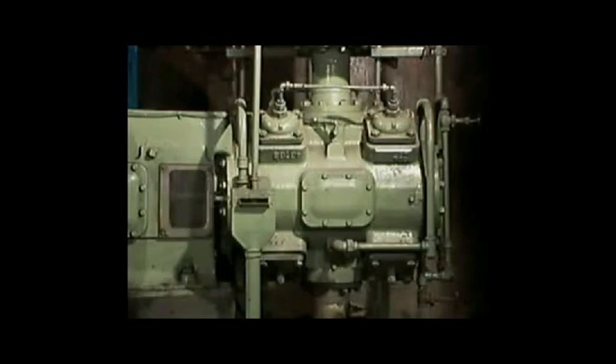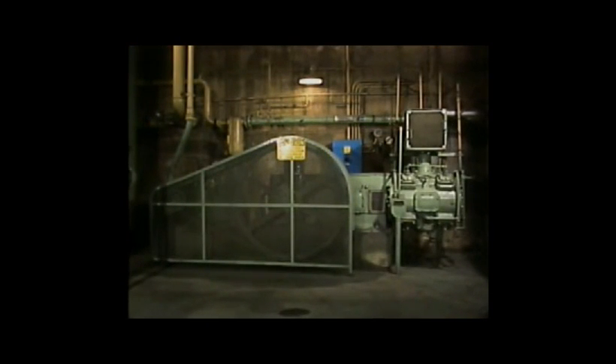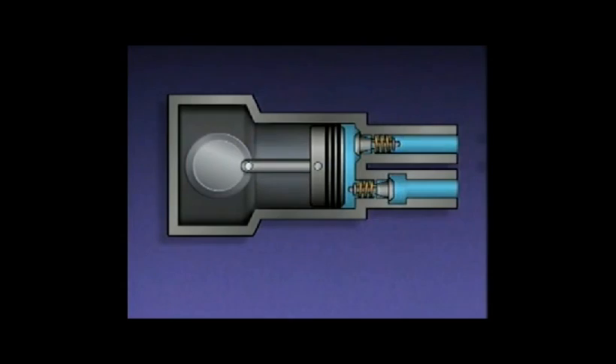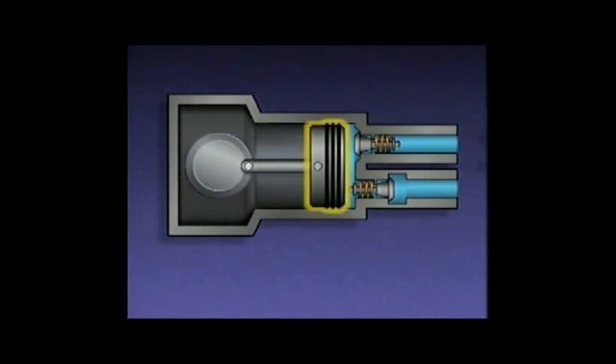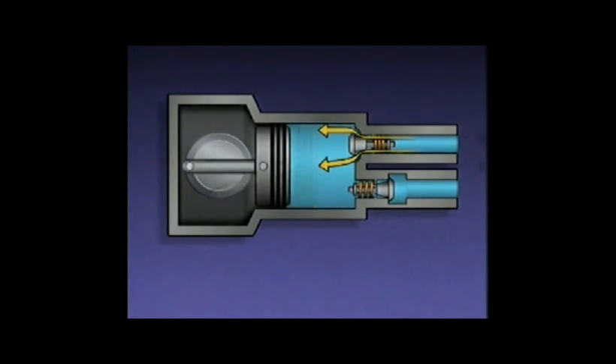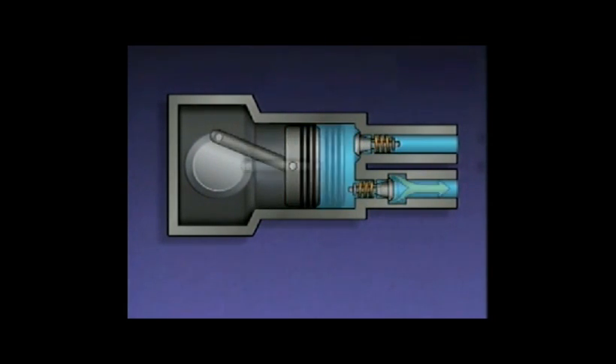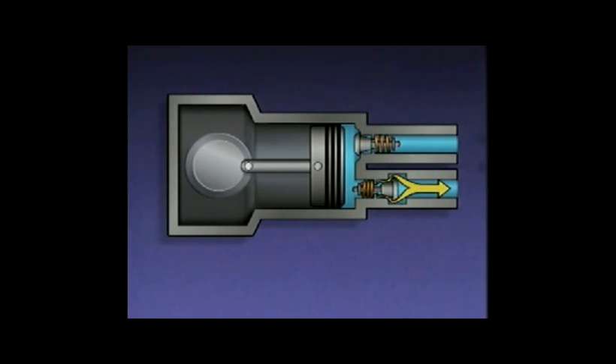Compressors can be divided into two general categories: positive displacement compressors and dynamic or centrifugal compressors. Positive displacement compressors work by trapping a certain amount of gas and forcing it into a smaller volume. A common type is a reciprocating compressor, which uses a cylinder and a piston. Gas enters the cylinder, is trapped inside, and is then forced into a smaller space by the piston, increasing its pressure. The compressed gas is then discharged.